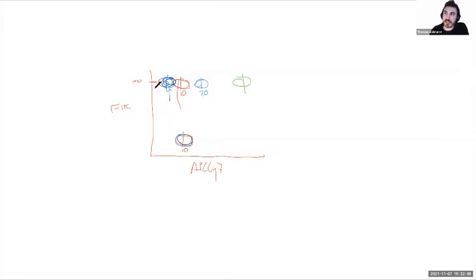So let's say this was one batch of beads, it had a lower autofluorescence, and this was a different batch of beads and it had a higher level of autofluorescence. That could absolutely cause this situation. And so before we've even started with compensation, it already thinks that they're different. The other option is, depending on exactly what's happening, if for instance these were beads and these were cells, then it could give us some kind of mismatch like that again, because the inherent autofluorescence is going to be different. So I think those would be the main things.